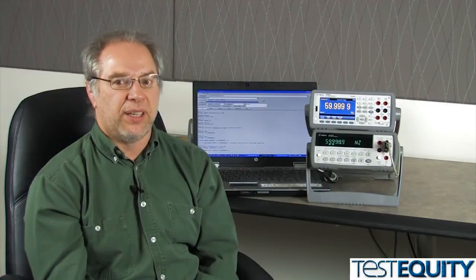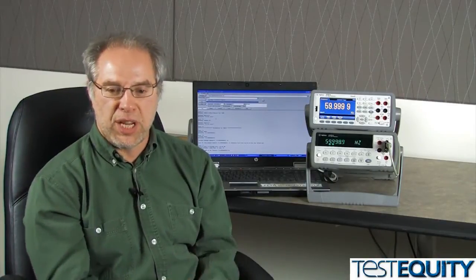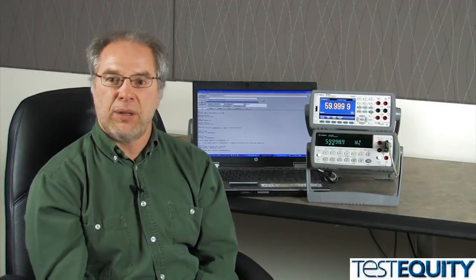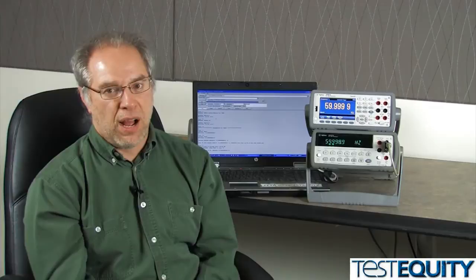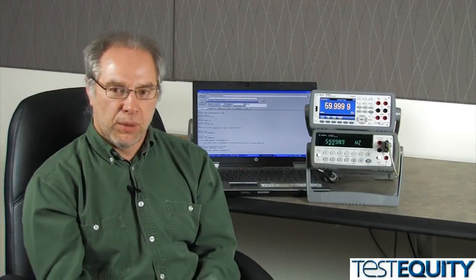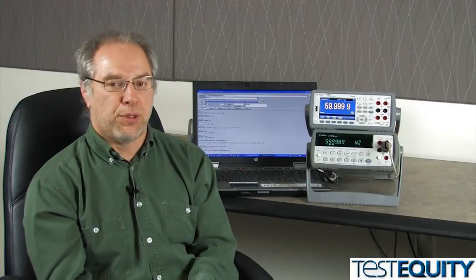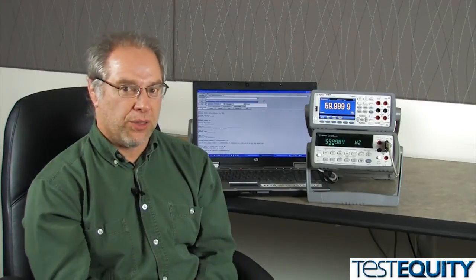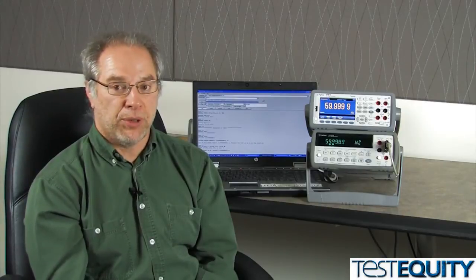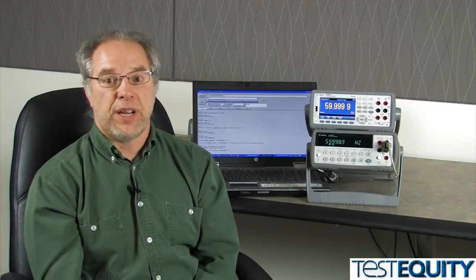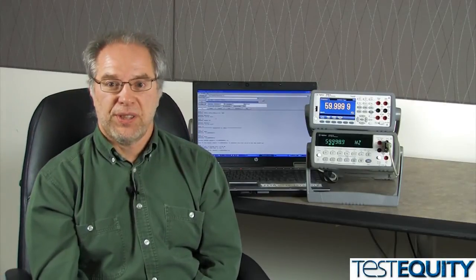In my testing assignment, I put a new DMM on our existing regression test, ran hundreds and hundreds of tests to verify that the new DMM works the same as the old one. All the existing commands for the 34401 are going to work on this box. So this demo is just a small sample showing you the compatibility, but we have done some very extensive testing on compatibility so that you won't have any issues. Thank you very much.